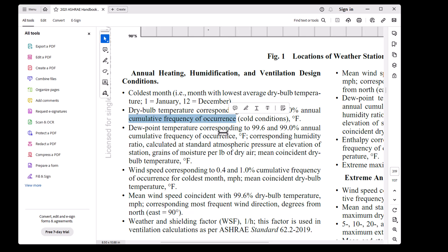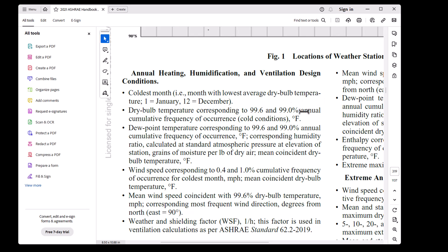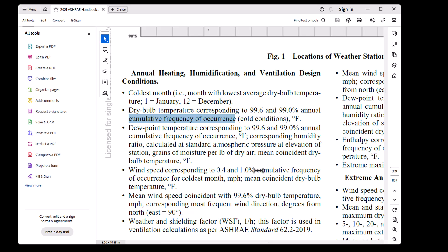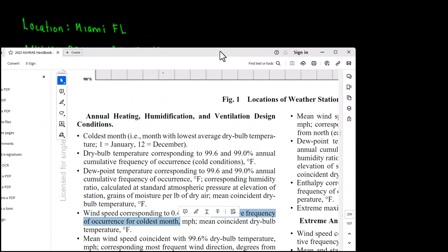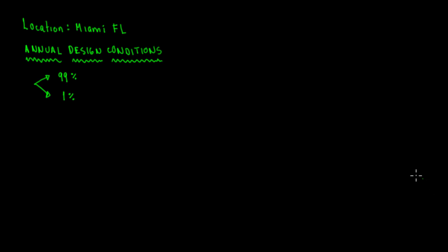From ASHRAE 2021 Fundamentals: the dry bulb temperature corresponds to 99.6% and 99% annual cumulative frequency of occurrence. That's the definition. Anytime you see 99% or 99.6%, it refers to annual cumulative frequency of occurrence. The same applies to 1% and 0.4%, which refer to cumulative frequency of occurrence for the coldest month.